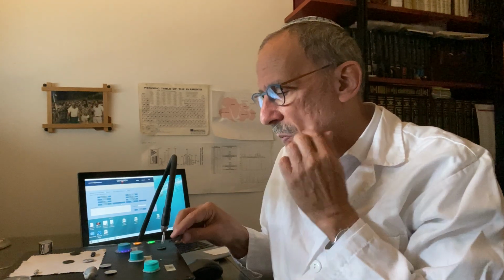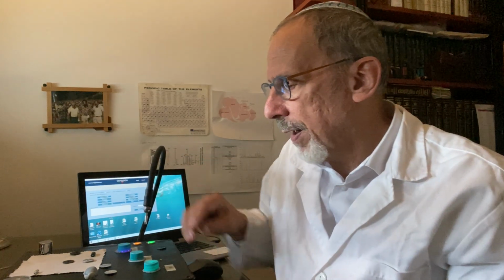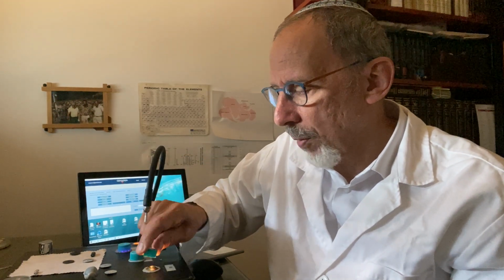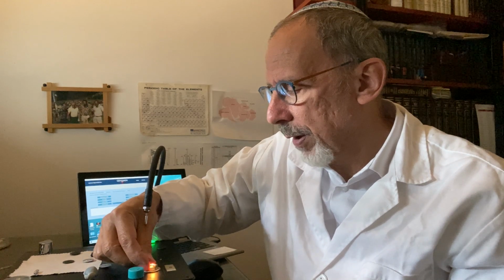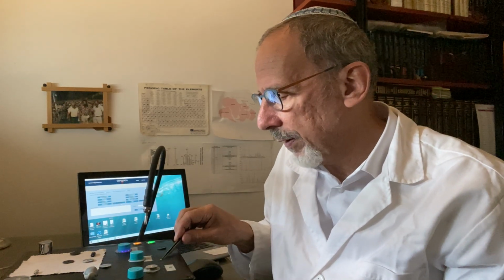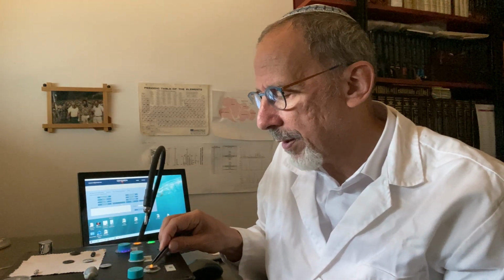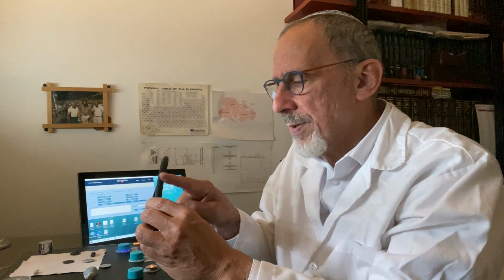round orange stone. And the first thing we're going to do is measure it on the white light source. So we put a little aluminum disc. The aluminum disc has a little hole in it that allows light to come through. It's a little smaller hole than the diameter of the stone.